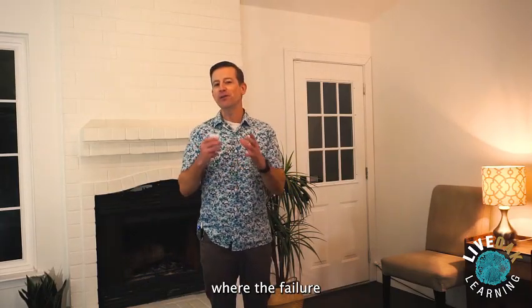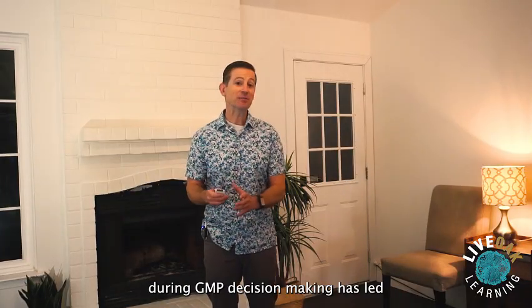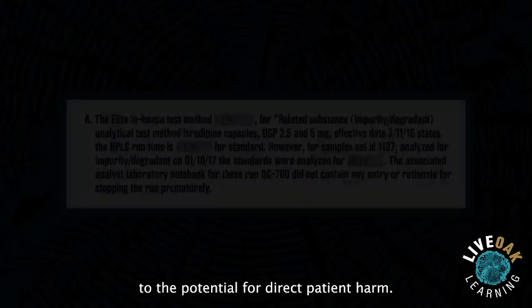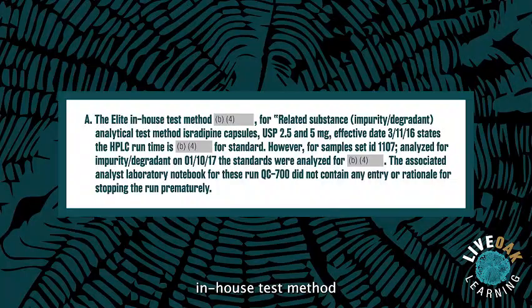Here is an FDA Form 483 observation where the failure to consider complete data, in this case non-routine data or metadata, during GMP decision-making has led to the potential for direct patient harm. The in-house test method for related substances, an analytical test method for these particular capsules, states that the HPLC runtime is this many minutes for this standard.